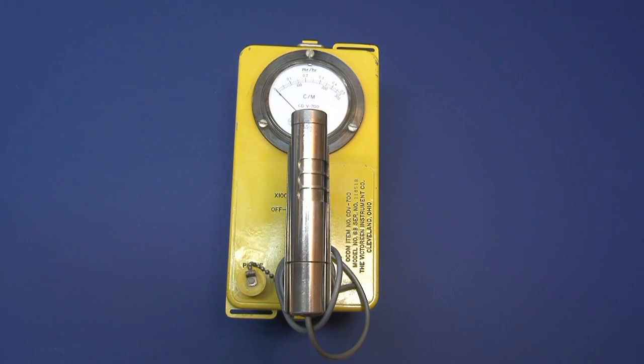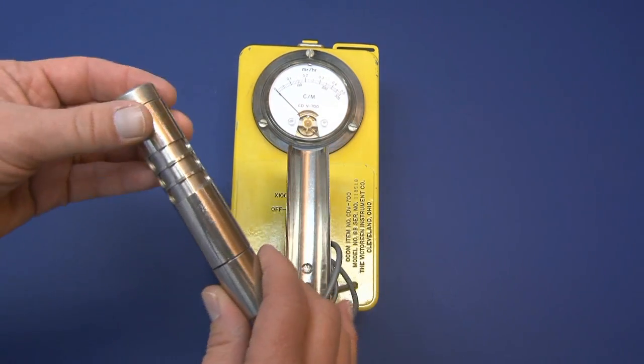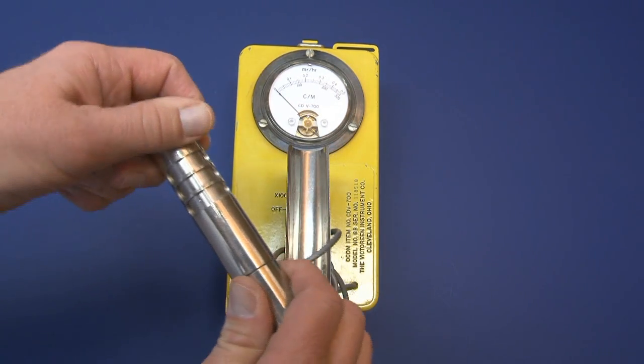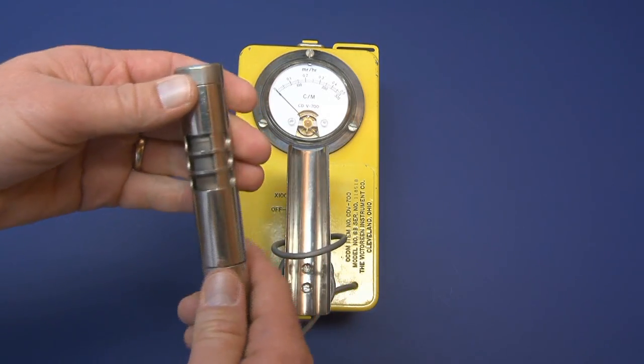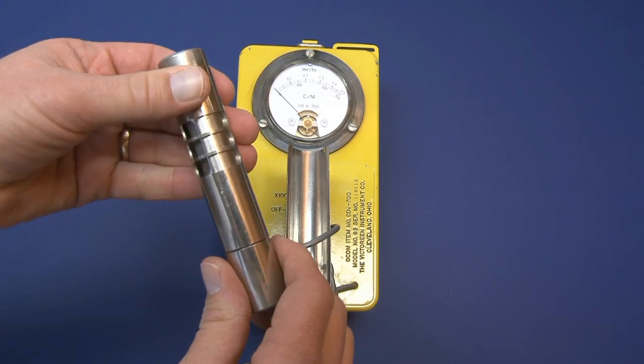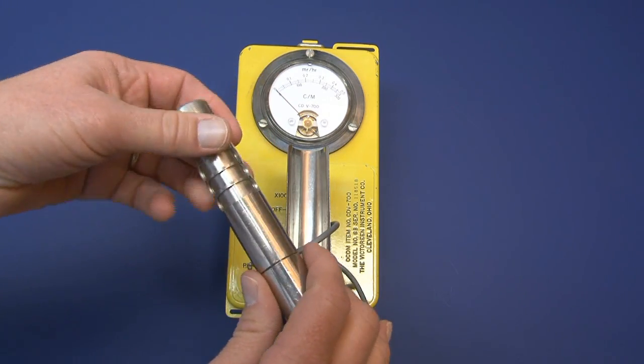Let's take a look at some of the features of this instrument. The instrument employs a nickel-plated brass rotary shield over the GM tube. This allows for either radiation exposure rate measurement or contamination surveys, and allows you to distinguish between beta and gamma radiation.